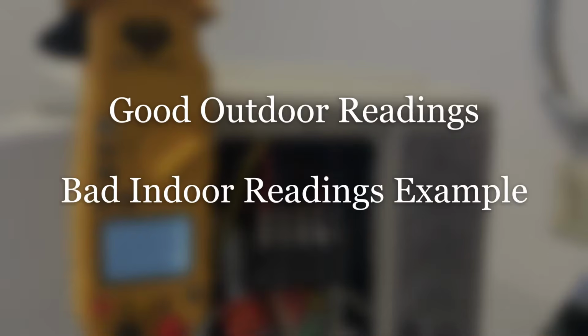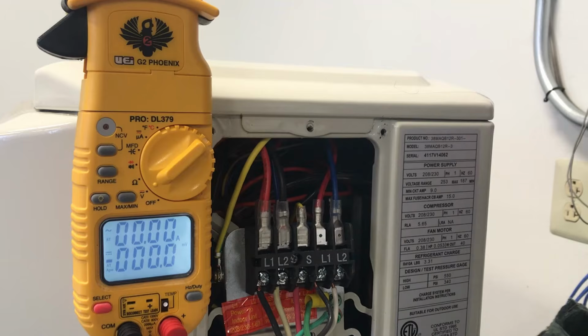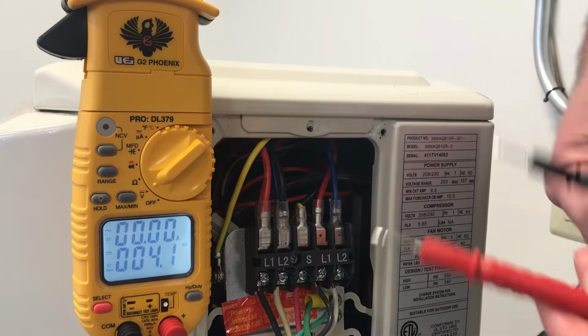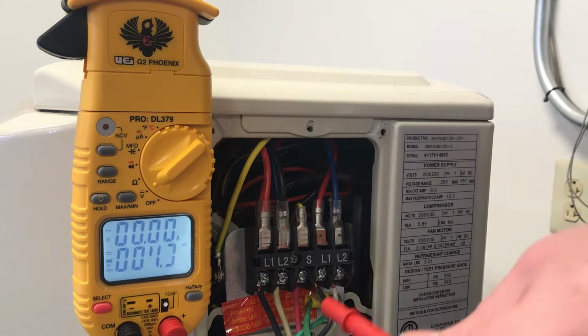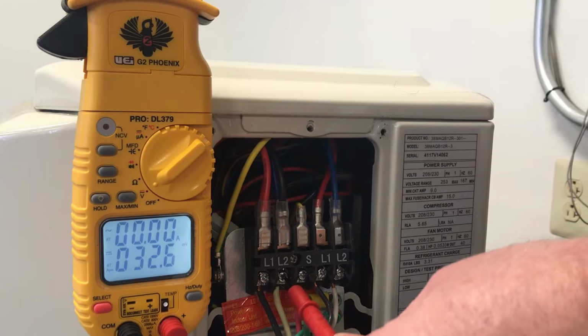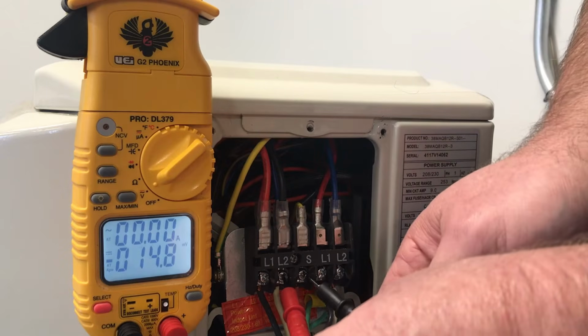All right, so earlier we showed you what a communication problem looked like when the outdoor equipment was the problem. Now we're going to take a look at what the communication issue would be if we had a problem with the indoor unit. So we're going to still take the same DC reading across L2 and S. L2 is red, S is your black lead.